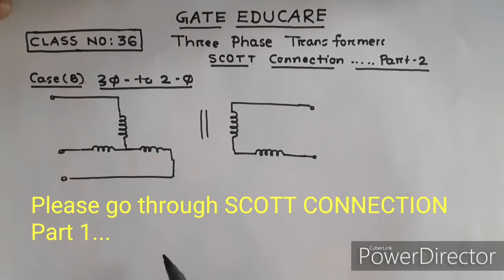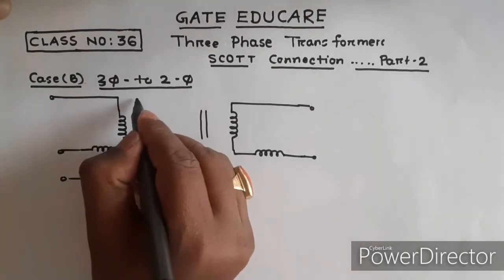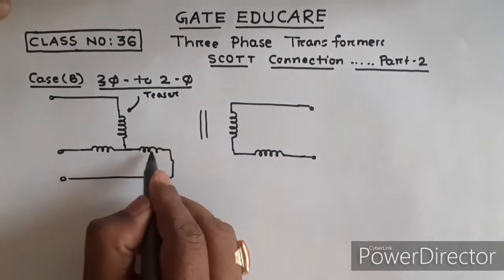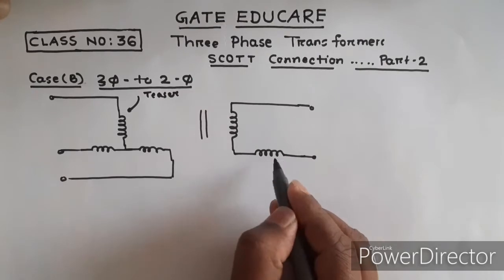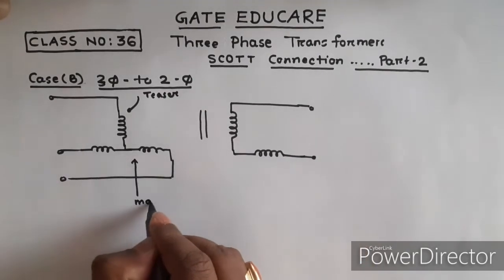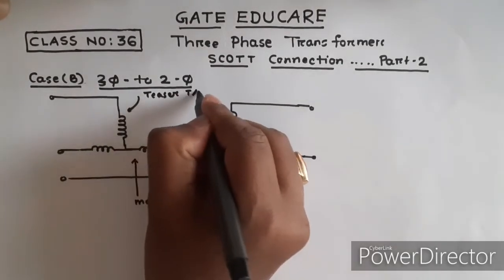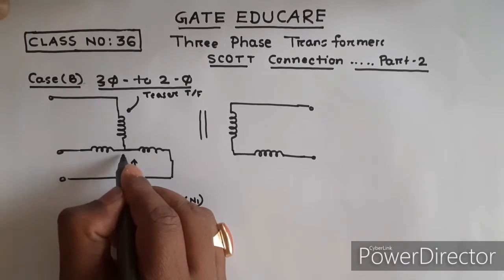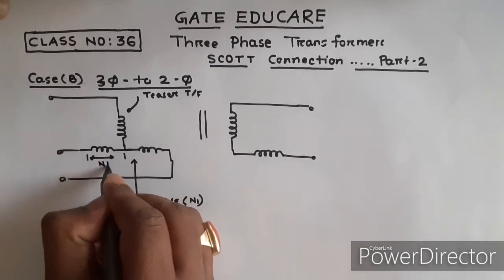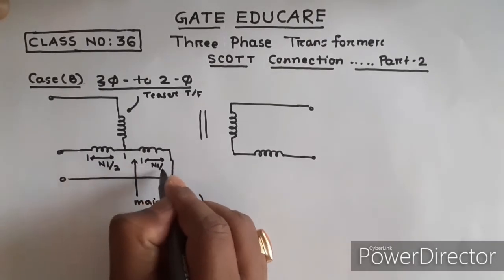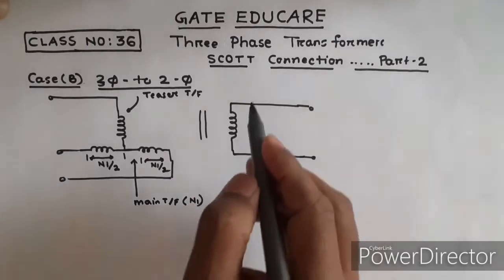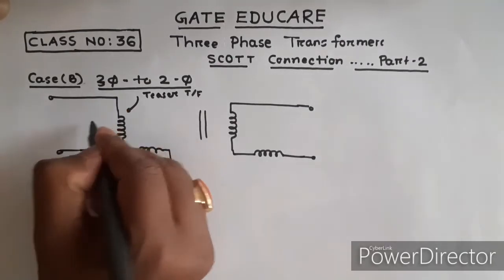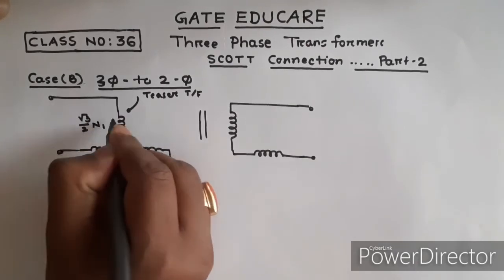As explained earlier, this is the primary of the teaser transformer and this is the secondary of the teaser transformer. This is the primary of the main transformer and this is the secondary of the main transformer. If the main transformer primary has N1 number of turns, it should be center-tapped, meaning each half has N1/2 turns. The teaser primary winding has root(3)/2 × N1 number of turns.